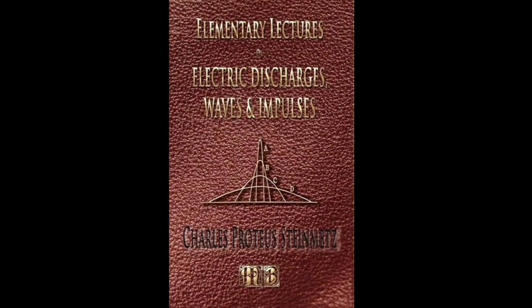In the transients resulting from circuit changes, as short circuits, the self-inductive armature reactance and the magnetic armature reaction act and vary differently. The former is instantaneous in its effect, while the latter requires time. The self-inductive armature reactance X1 consumes a voltage X1I by the magnetic flux surrounding the armature conductors, which results from the MMF of the armature current, and therefore requires a component of the magnetic field flux for its production.